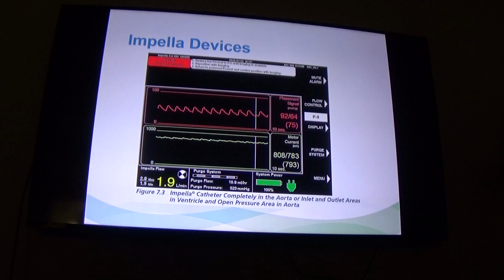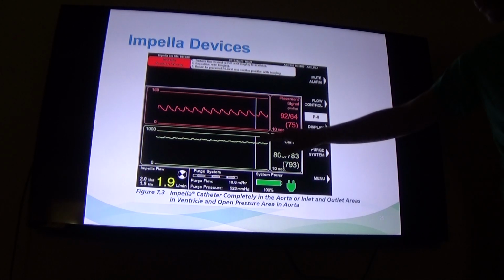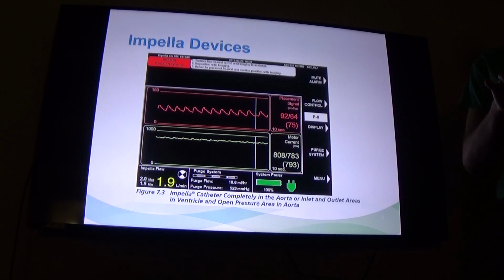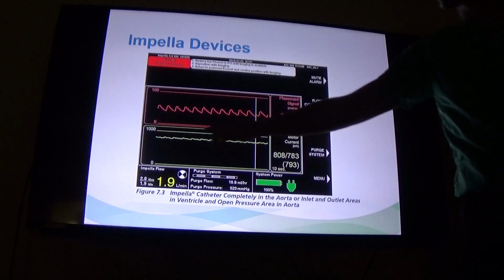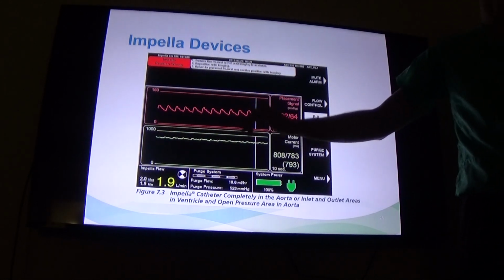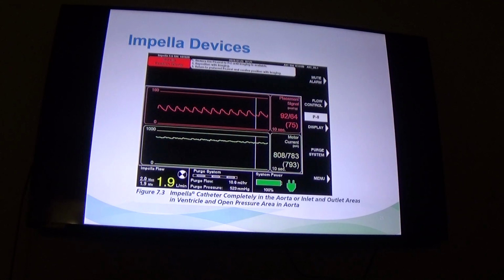We want to use our ultrasound, and again, you would know how to advance just like you would for a transvenous catheter. If it's fairly close, or you can see the device sitting right at the aortic valve or right across it, yes, we could advance it just a little bit. And when we do that, what we're going to see is just a slight advance, very slowly, 1 centimeter at a time, until you see that motor current start up again. And then you'll know, hey, I'm across. Again, tighten down your clamp, and you'd be in the right place.